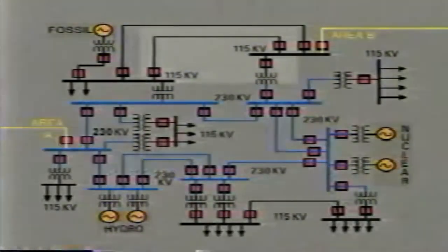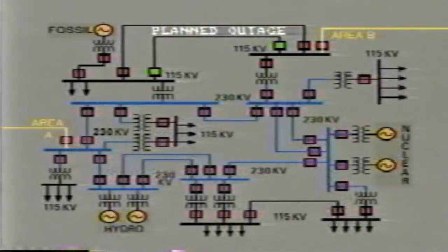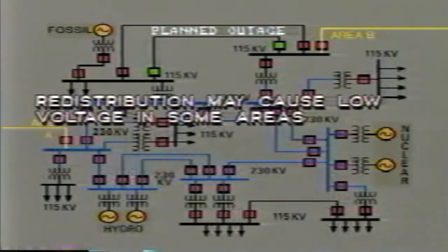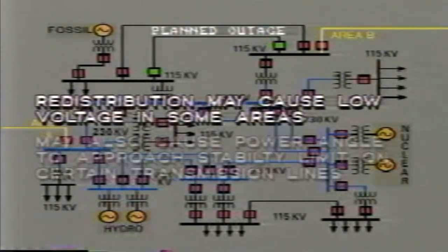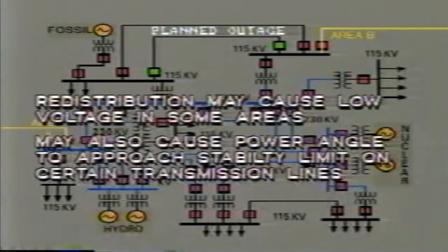Outage of transmission lines will also cause problems due to redistribution of the load flow throughout the rest of the system. This may bring problems of low voltage in some areas and may also cause the power angle to approach the stability limit on certain transmission lines. Of course, a certain amount of reserve is built into the system.